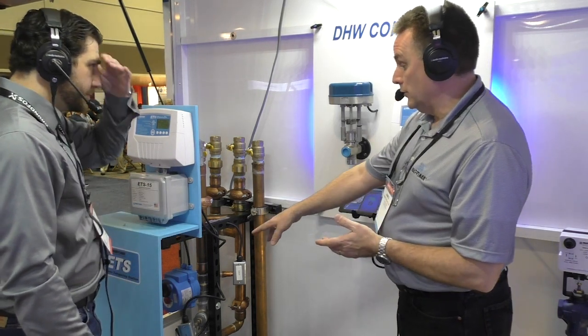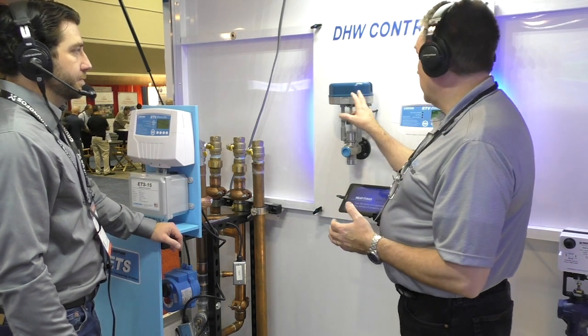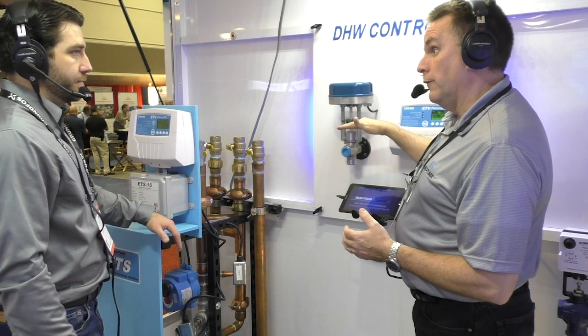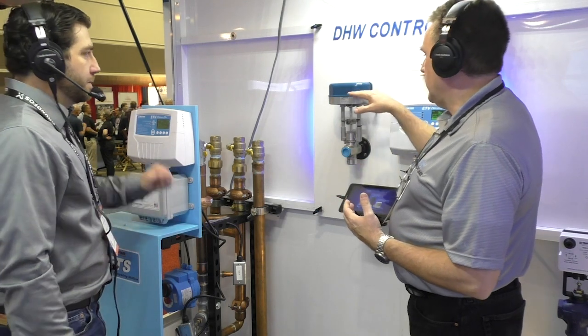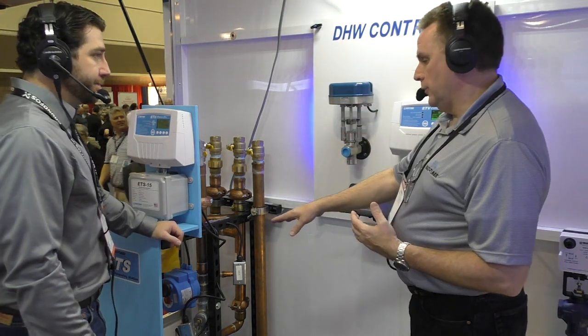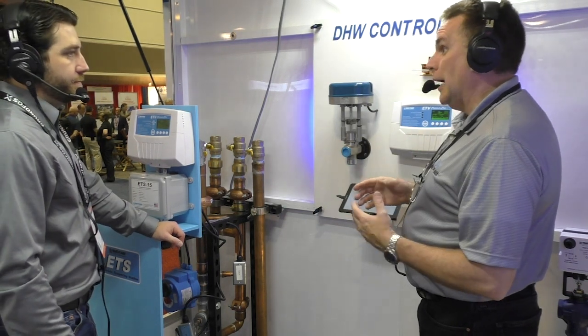Every ETS, again, comes with a TMC valve. That has a battery backup in it. So if we lose power, the ETV actuator, the valve actuator itself, has a capacitor in it. It will drive the valve to full cold. Right. To avoid any type of creep or anything like that, we have 100% shut off on the TMC valve. Now, again, if we set a high temperature limit in there and we hit that high temperature limit, the ETV valve will drive full cold and the TMC valve will go shut. When that happens, it is a manual reset on the control. When power is lost, once power comes back, everything goes back into its normal operations.